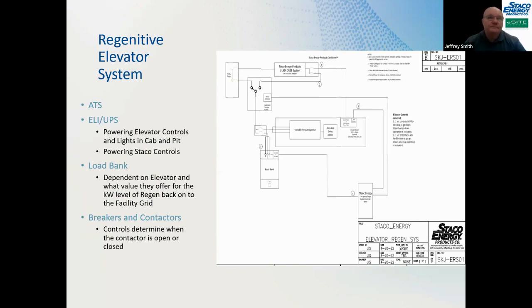We have, I want to say, about 60 of these units that are feeding elevator systems that basically go from where it's at right now to the next floor or to the bottom and stop. This last January 2023 is when California put in place that they want it to run for 2 hours. So this is when we have to increase the battery runtime and the capabilities to make sure that, with the regenerative load that's being fed back, the elevator can go up and down for 2 hours and still bleed off that regenerative power, so we don't take a chance of damaging any part of the UPS. So this is what we're looking at.